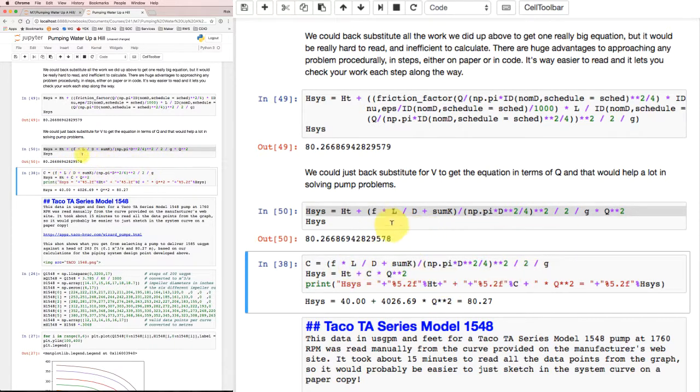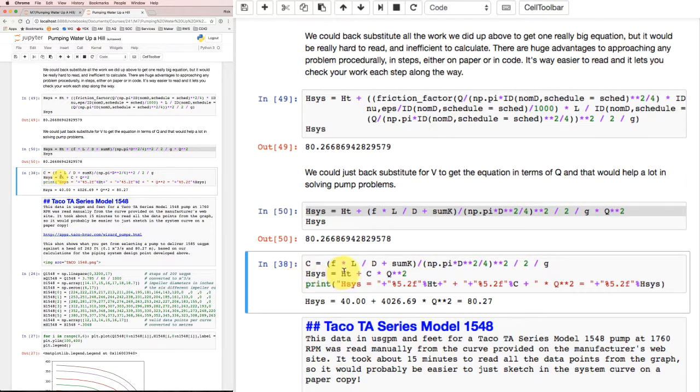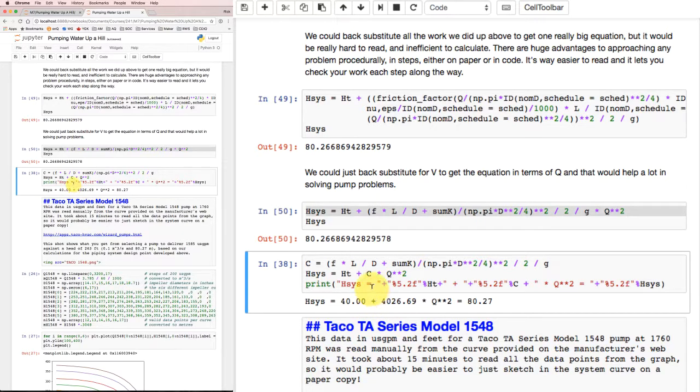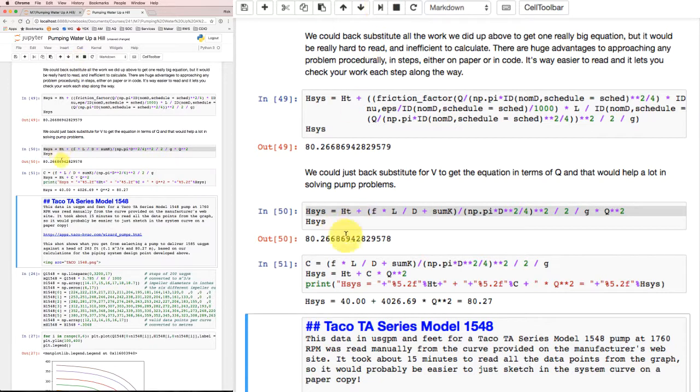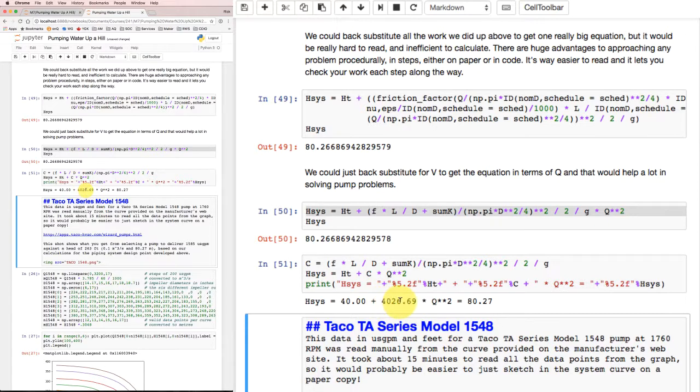Finally, if I wanted to, I could take this stuff that's multiplying times Q and calculate it as a separate constant and just get the system head as the head rise to overcome the elevation plus some other chunk that varies with the flow rate squared. That was the equation I found would be simple to put up onto our pump characteristics to see where the two intersect. So finally, I can do this calculation, and there's the equation I got on paper. The system head must equal the elevation I need to overcome, those 40 meters, plus 4026.69, which is basically 4027, times Q². That gives my overall result of 80.27 meters head rise across the pump.